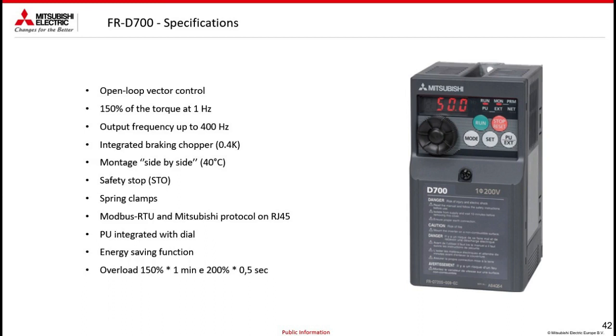Side by side mounting at 40 degrees, so they can be placed side by side with minimum distances, but with a maximum of 40 degrees centigrade inside the panel. Safety stop, safety torque off, therefore double safety channel input with the function that safely disconnects the power section and therefore the motor. Very comfortable spring clamps, includes an onboard serial port for Modbus RTU or Mitsubishi protocol with the RJ45 connection.